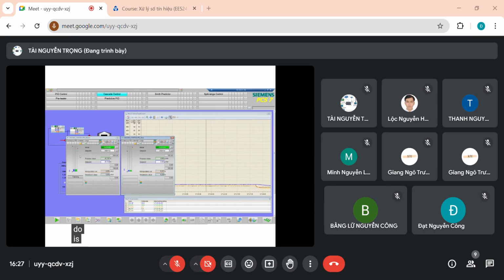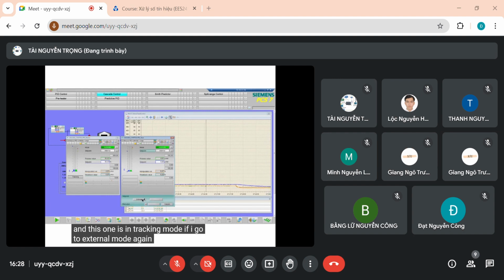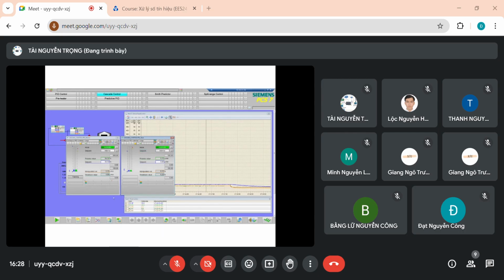So what you will have to do is make sure that this controller goes into tracking mode or input lock mode, and you can see that it has done this. You can see here tracking mode and the T appearing here. Okay, so the PID control algorithm has become inactive, and the output of the controller is actually, in this case here, the process value of this. We will see this later. You can see here that the manipulated value is now tracking the process value, and this one is in tracking mode. If I go to external mode again, this controller will be acting again, will be controller, and you will see here that this tracking will be disappearing.